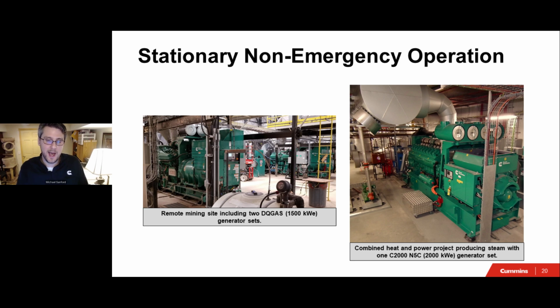It doesn't exist. Alternatively, an application like a combined heat and power project, where the generator is operating in a base load configuration and also providing heat to be transformed into steam for hot water or whatever it may need to be, is also considered non-emergency because it's not operating only when the normal source has failed. It is operating alongside the normal source. Because non-emergency operation could potentially be for greater duration, in fact, it's unlimited. There's no limit to the amount of operation that a non-emergency certified engine could operate.